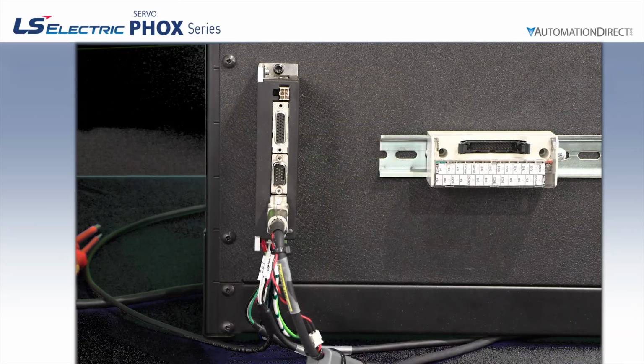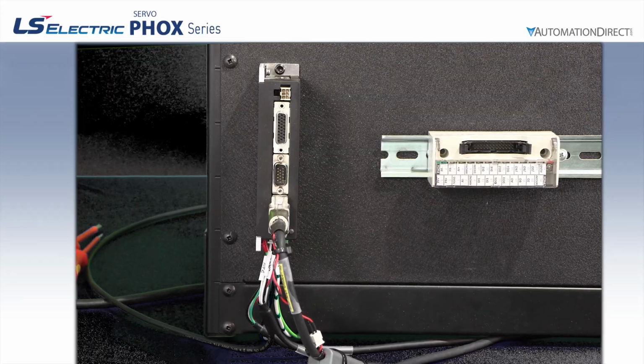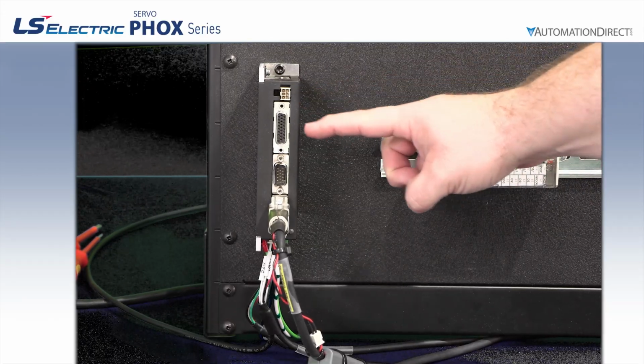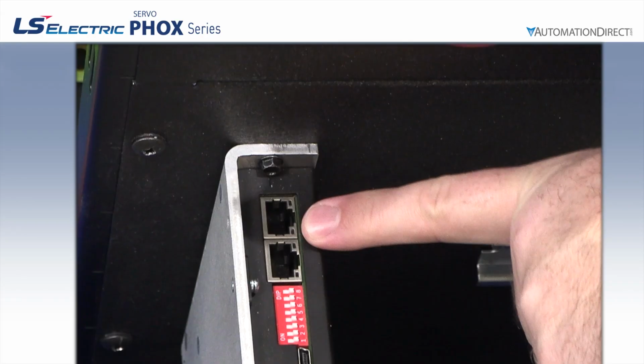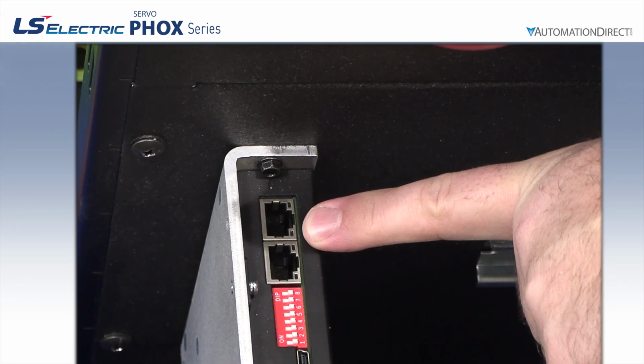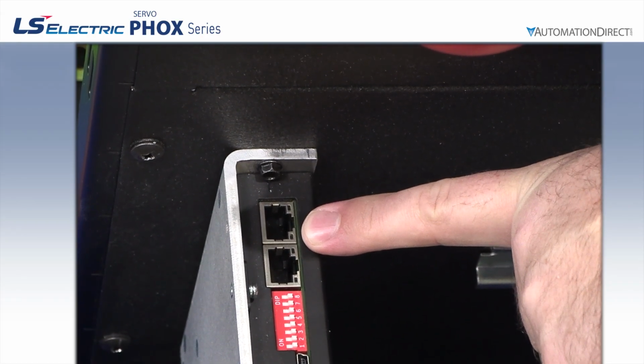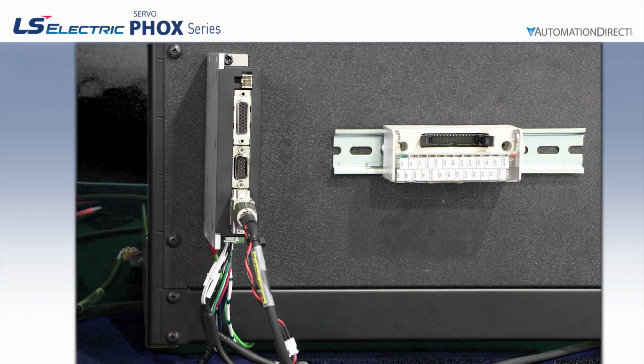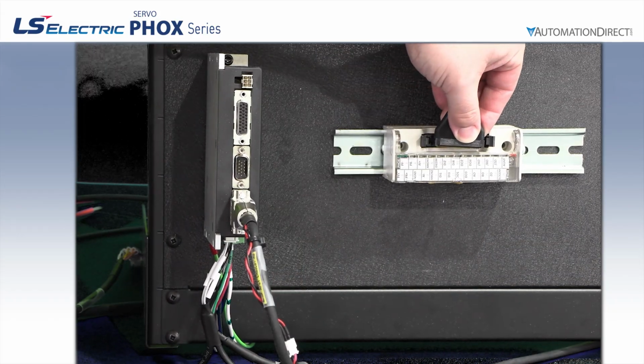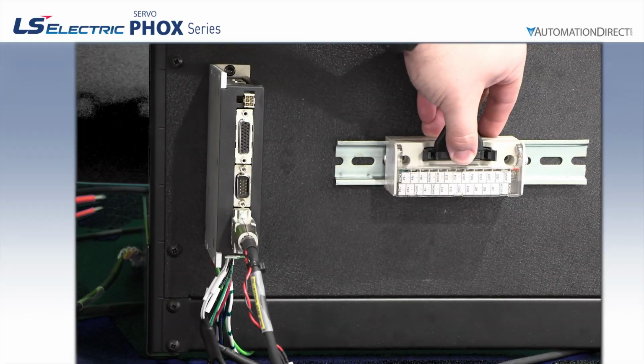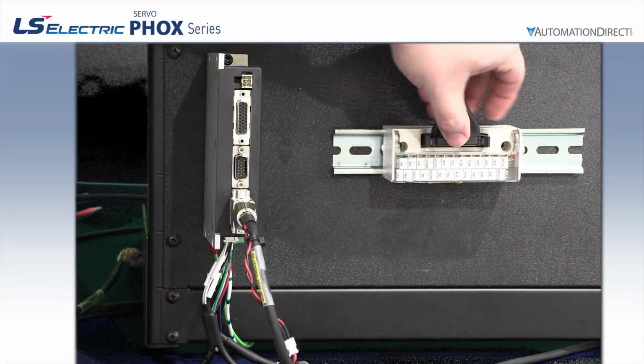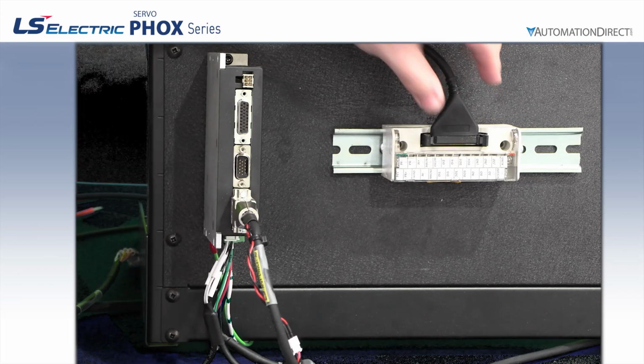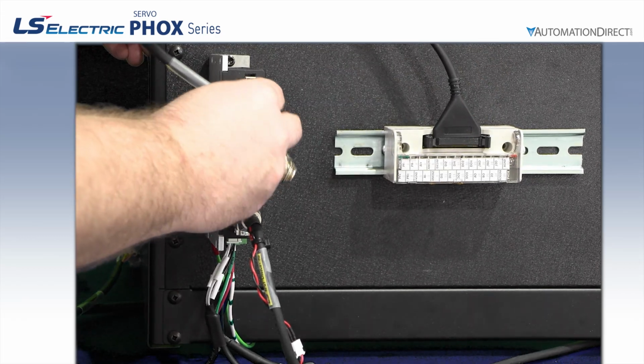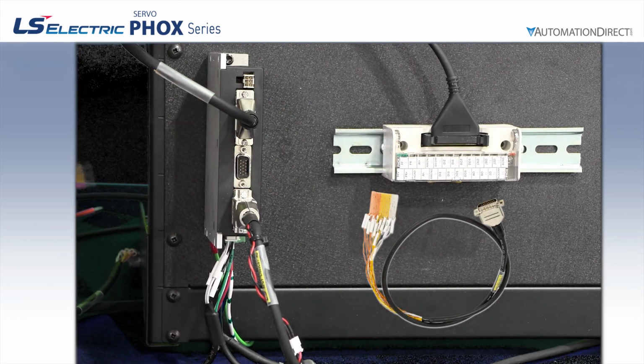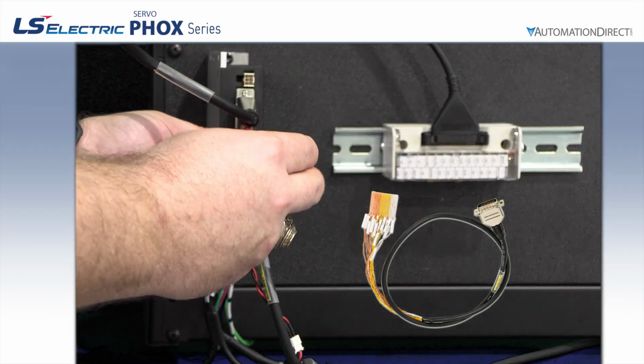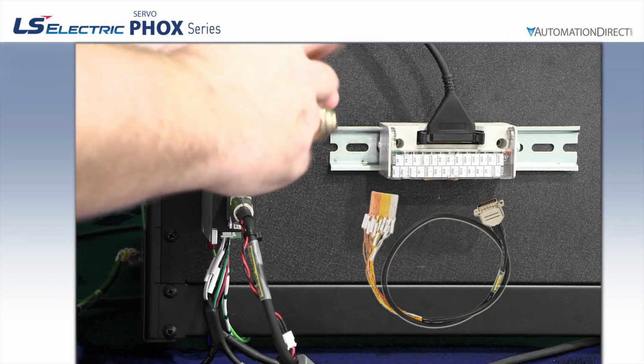heatsink. Looking at the drive now, the only connections we haven't made are the STO, I/O, and 2 EtherCAT RJ45 jacks. We aren't using EtherCAT for this example, so we'll leave those alone. We are using I/O, so now we can install the pre-made I/O cable and terminal block into the drive's I/O terminal. Mount the terminal block onto the DIN rail next to the drive and land the other end of the cable. Another option would be to use the pigtail cable if only a limited subset of wires is needed, or you want to use your own terminal blocks in your enclosure.